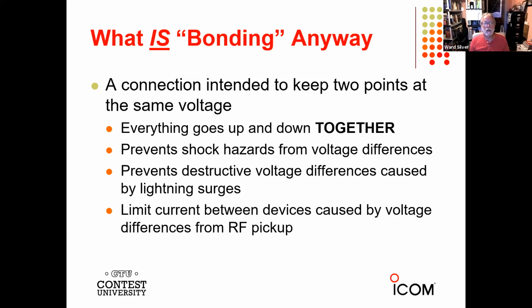In lightning, you want to prevent the destructive voltage differences caused by lightning surges. And you hear stories about suddenly a giant arc jumps between one point in the house and another point, and now nothing works. It's because the pieces of equipment were not bonded together, so that suddenly there was several kilovolts of voltage between the two of them, and there was an arc, and that caused the problem. So you prevent the destructive voltage differences from lightning by bonding things together. And as I just mentioned, you limit current flow between the devices caused by voltage differences, and that's what causes RFI. It's not the voltage, it's the current, and the common mode current that flows into things where it should not flow into.